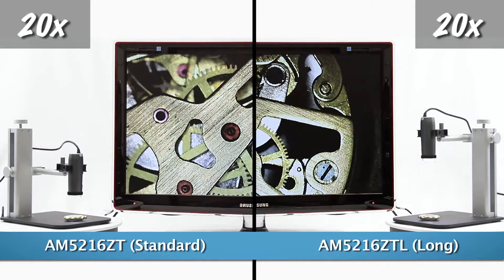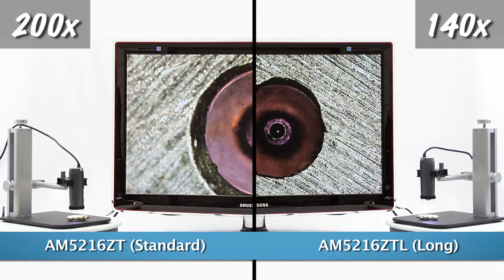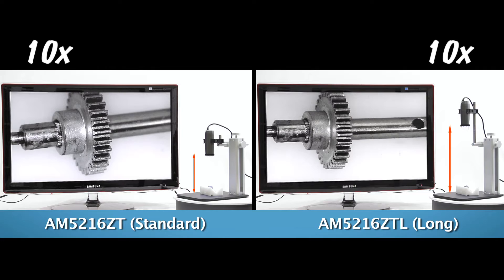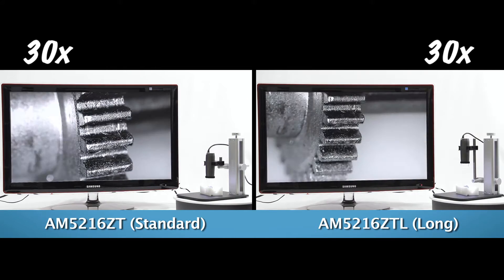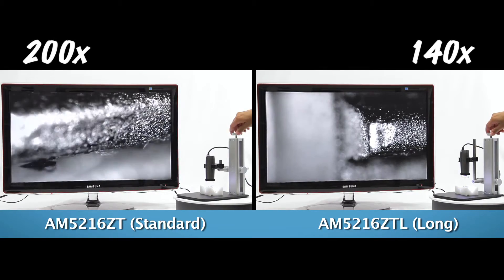The AM5216ZT is a standard working distance model with a magnification range of 20 to 200 times. The AM5216ZTL is a longer working distance model, meaning there is increased distance between the end of the microscope and the object in view. This model has a magnification range of 5 times to a maximum of 140 times.